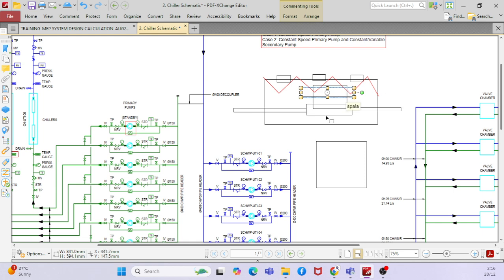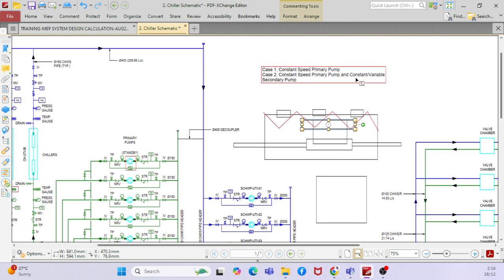So in this heat exchanger, there will be refrigerant. Instead of air, there is another circuit called the condenser circuit, where you have a condenser pump and a cooling tower that rejects the heat. Essentially, within air cooled chillers, the entire refrigeration cycle is within one equipment.